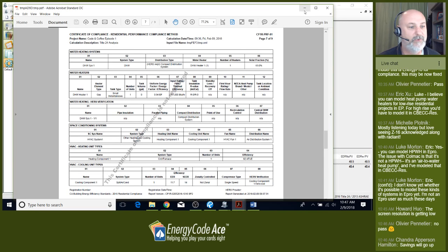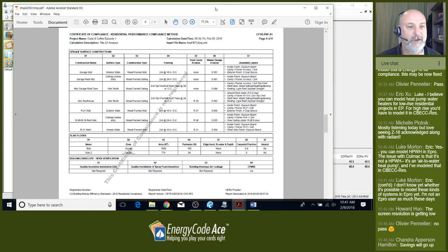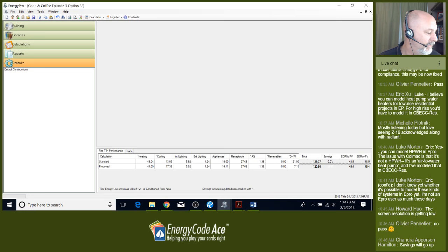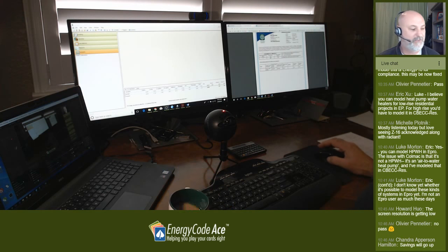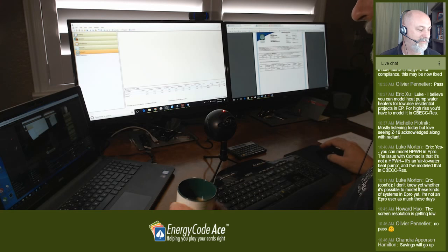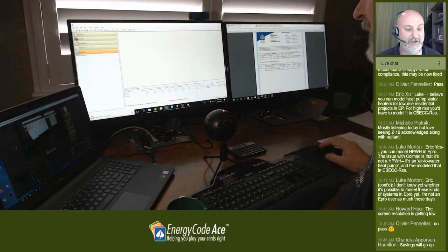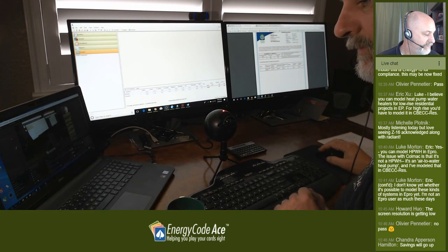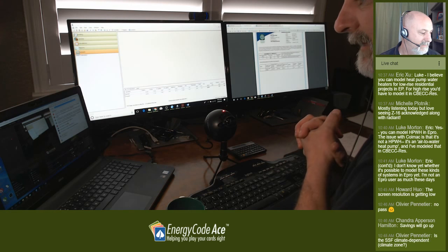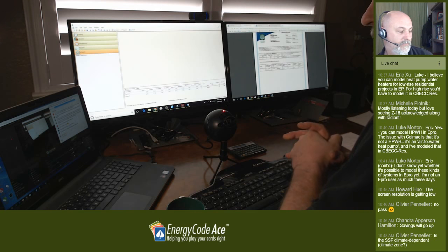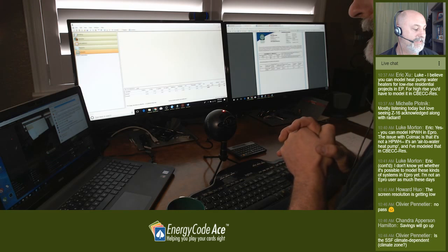All of these versions did require HERS verifications, which also requires documentation registered with a HERS provider. Olivier's question: is the solar savings fraction climate dependent? Yes, it is. When I searched the SRCC directory, I searched for a climate-specific system. The OG-300 certifications are climate-specific annual solar savings fractions. If you change the location — say, climate zone 7 in San Diego — the same make and model may have a different solar savings fraction.